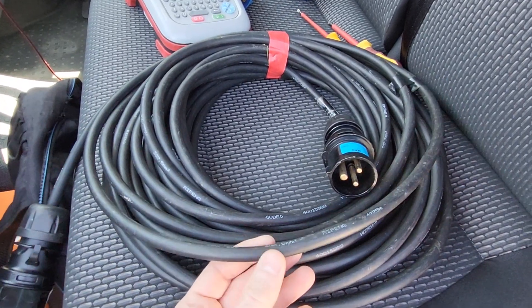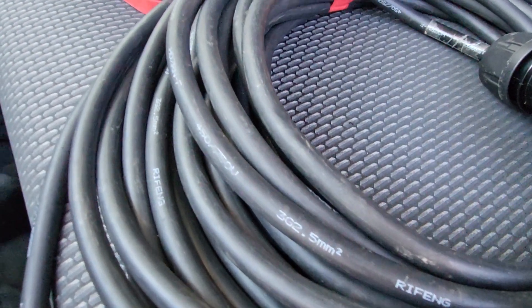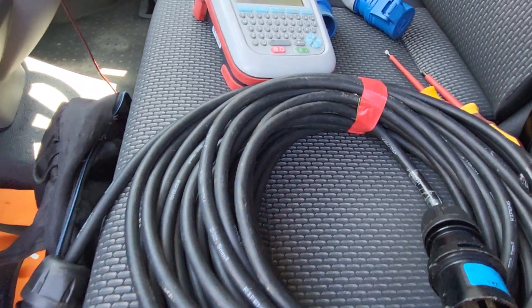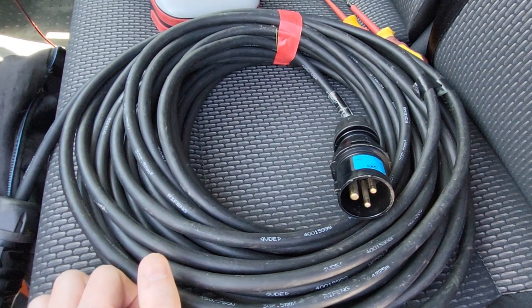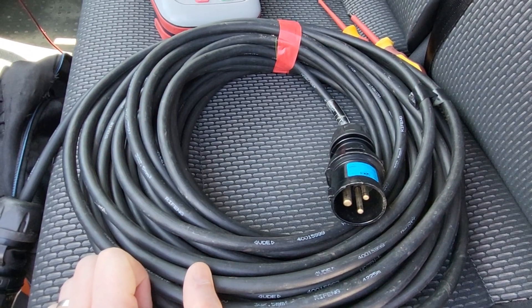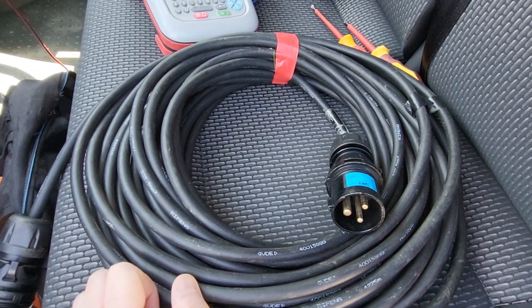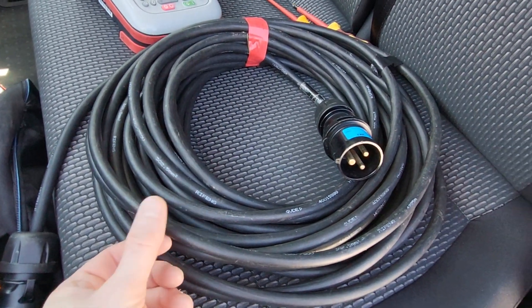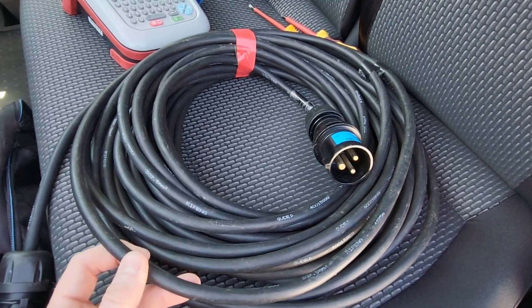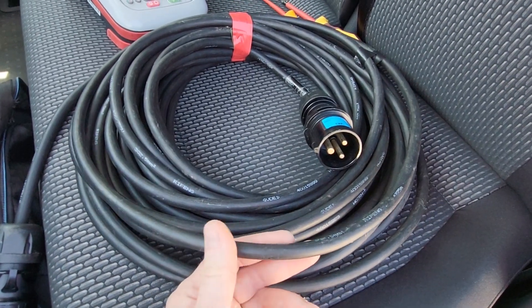Another thing to look out for is actually the type of cable. This type of cable here is called HO7RNF, and that basically means it's a definition of the type of cable it is. This particular cable is a rubber cable, which gives it better longevity in extreme conditions. There's a whole table online with different types of cable. The two main types you'll come across are a blue flex, which is called Arctic cable, and then this one which is H07.